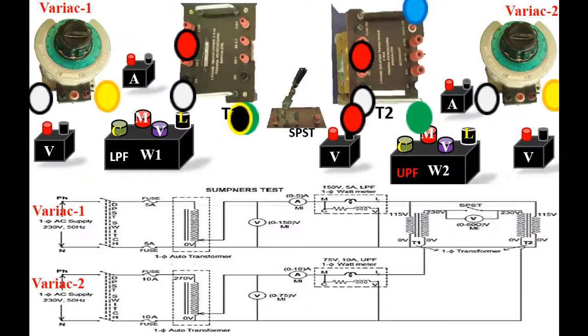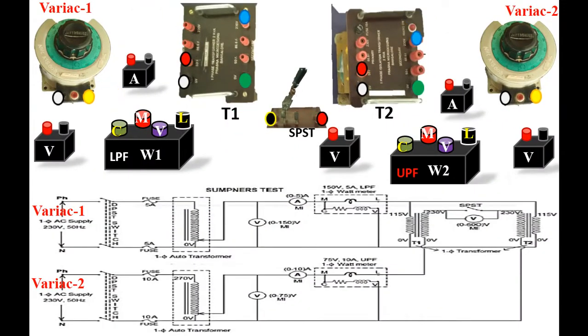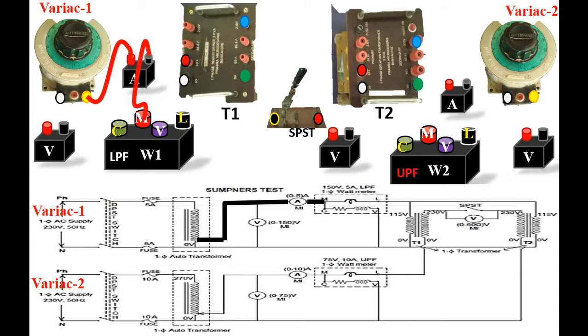Now let's see how we connect. From variac 1, the output of variac 1, I repeat, the input is given a raw single phase AC supply. The output of the variac, which is variable, is taken and given to one end of the ammeter. That is from variac 1 to the ammeter, and from the ammeter it goes to W1 M, and then M and C are shorted using a patch cord, and then L of W1 is given to T1 115, that is 50% of 230, and then 0 of T1 is given back to 0 of your variac.